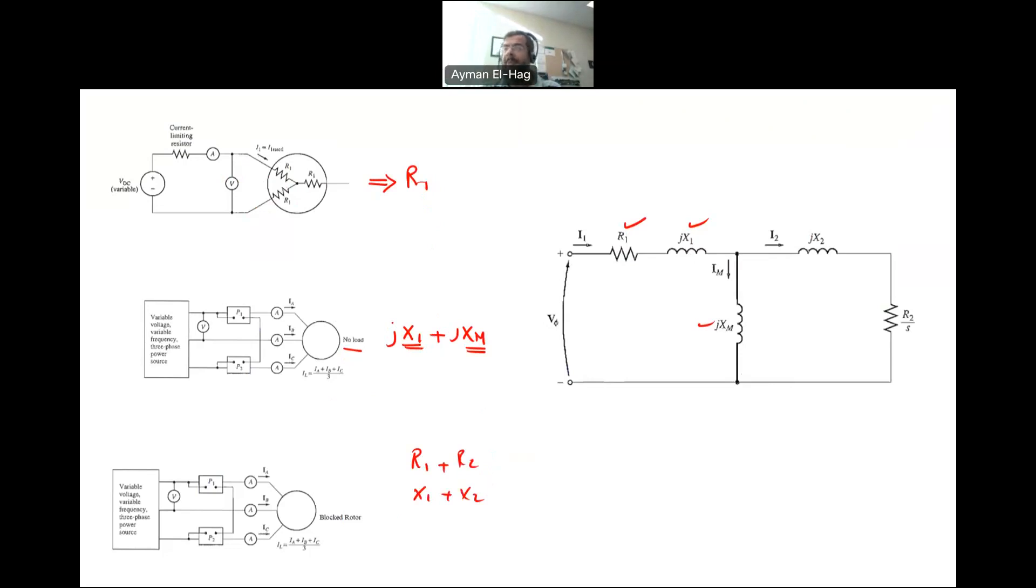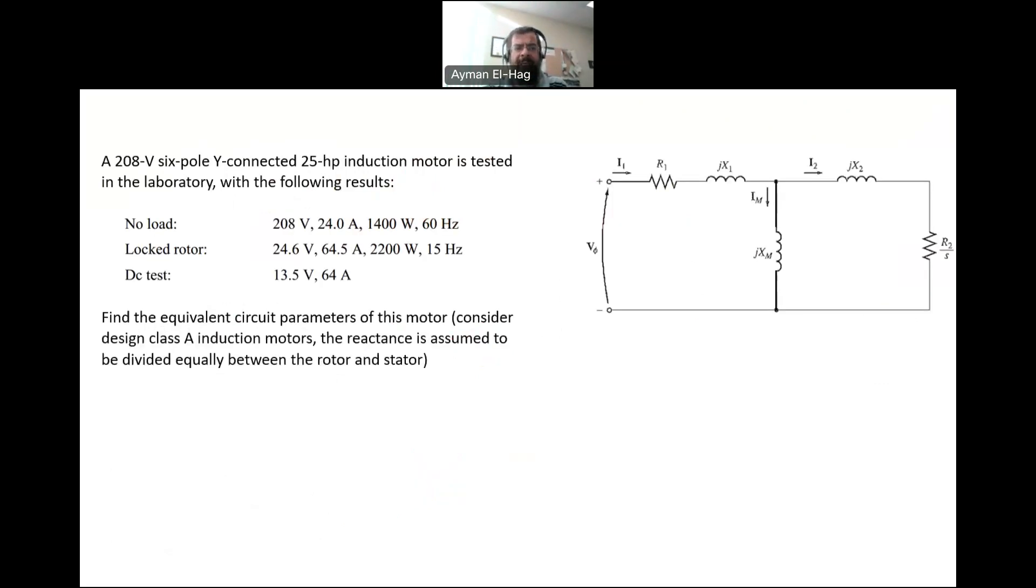It will also give us X1 plus X2. Usually there is an indication about the ratio of the two. If we have a type A motor, then X1 and X2 will be equal. Knowing X1, I will be able to find XM. This is how we use the tests to find these parameters.